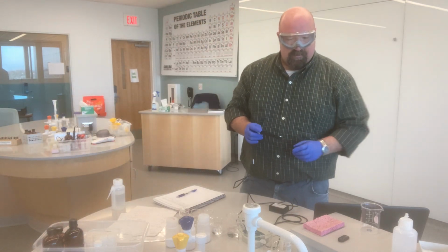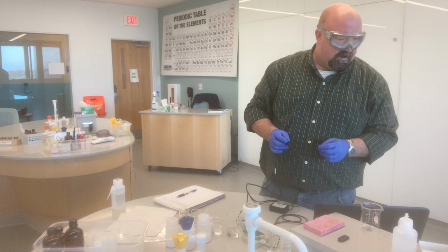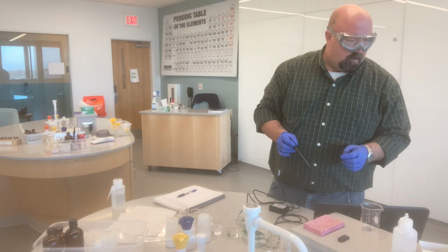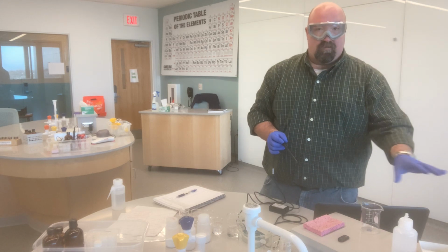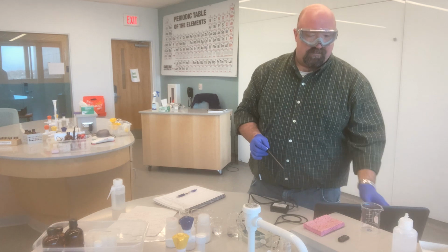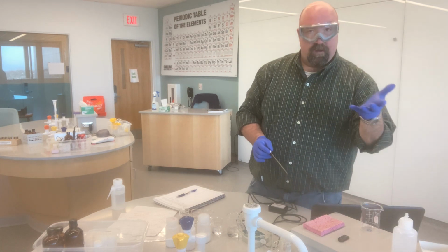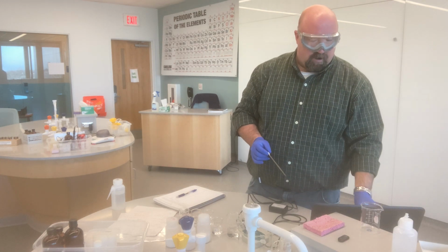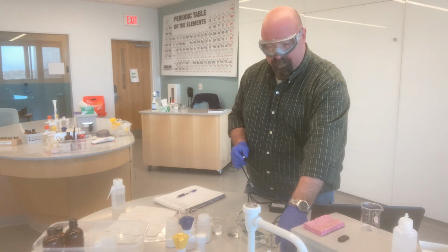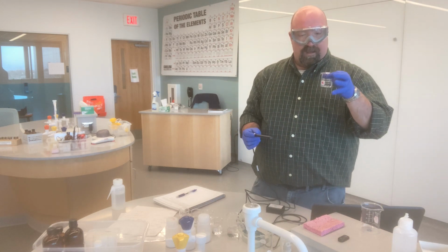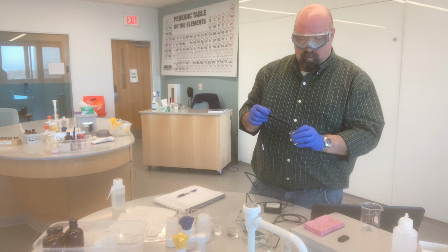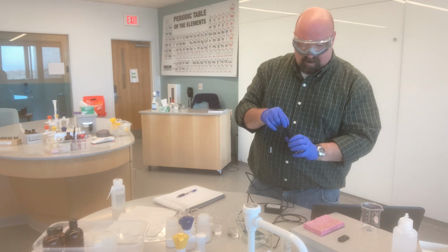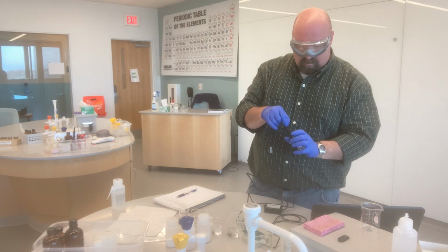And so, like I said, the first thing that we have to do is to calibrate the probe. I'm going to just follow the directions for calibration, although I've done this enough that I know what I'm doing. But if you were here doing it, you would simply follow our directions for calibrating the probe. We're using 2 points to calibrate. One of those is with distilled water, which just has a conductivity of 0.